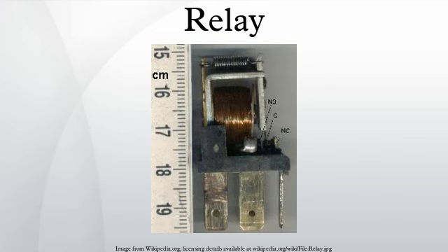Voltage rating of contacts: typical control relays are rated 300 VAC or 600 VAC, automotive types to 50 VDC, special high-voltage relays to about 15,000 V. Operating lifetime: the useful life, the number of times the relay can be expected to operate reliably. There is both a mechanical life and a contact life. The contact life is naturally affected by the kind of load being switched. Switching while wet causes undesired arcing between the contacts, eventually leading to contacts that weld shut or contacts that fail due to a build-up of contact surface damage caused by the destructive arc energy.